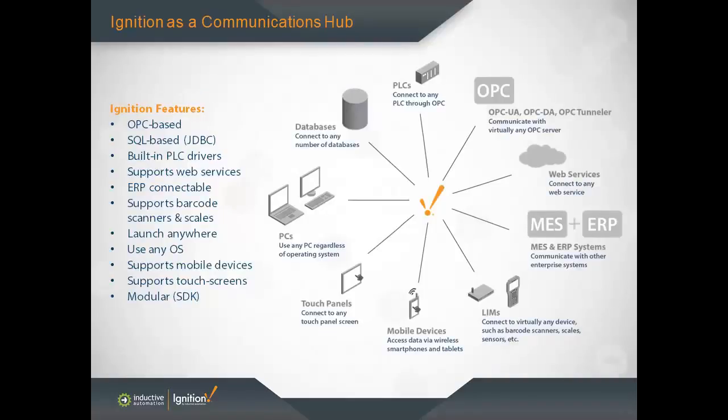Ignition can connect to any PLC through OPC. In fact, Ignition has a built-in OPC UA server with drivers to popular PLCs. Ignition can also connect to any third-party OPC DA or OPC UA server, allowing you to connect to practically any PLC that exists in the market. Ignition can connect to any web service. Typically, ERP systems expose web services that we can communicate to. Ignition can connect to any database, any SQL database, whether that be MySQL, Microsoft SQL Server, Oracle, Postgres, DB2, and more.